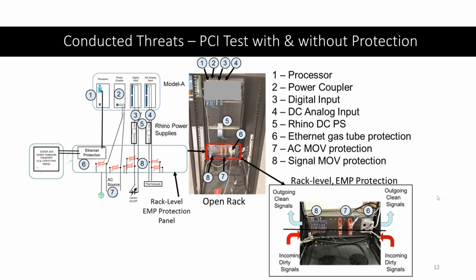So we did see that without the protection, eventually as you ramp up to the maximum of 5,000 amps of injected current during these tests, all the relays that we tested were destroyed. All the DCS components that we tested were destroyed. But smartly, before we did that, we tested with the MOV device in place, and that had a much better result. There were some upsets, both non-latching and latching, but nothing was destroyed up to the very top level. When we got to 5,000 amps, we were still able to break things, even with the MOV protection in place, but it performed much better. So we know that MOV protection is an option that will work. Next slide, please.